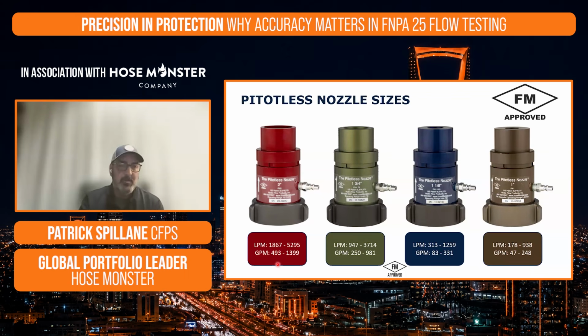So our flow range is going to be anywhere from 500 gallons a minute to upwards of 1,400 gallons a minute. And then stepping down to our 1 3/4, which is a very good sweet spot for a lot of fire pump testing, as well as probably for most hydrants around the world, at 250 gallons a minute to 981 gallons a minute, which again is going to be approximately 1,000 liters per minute up to 3,800 liters per minute.